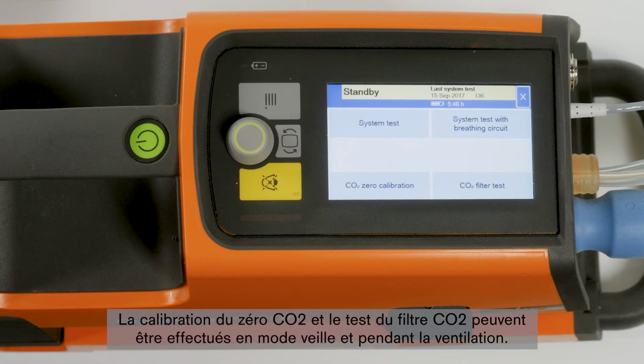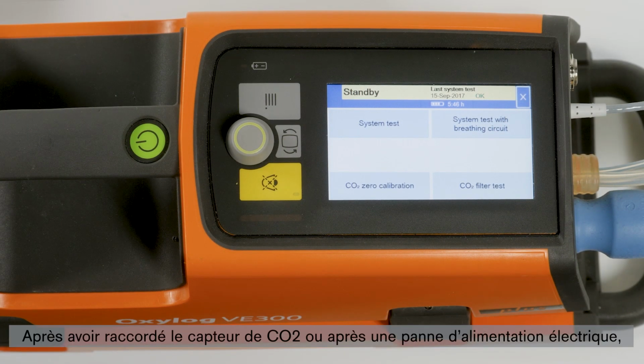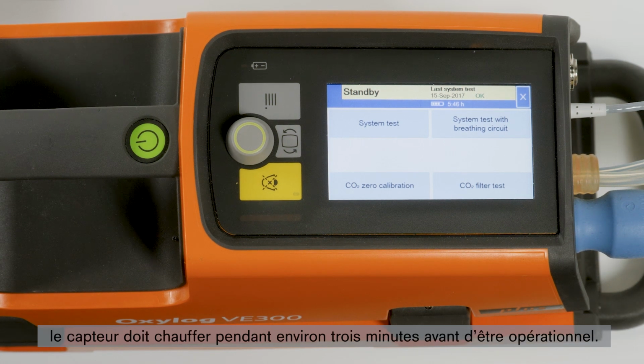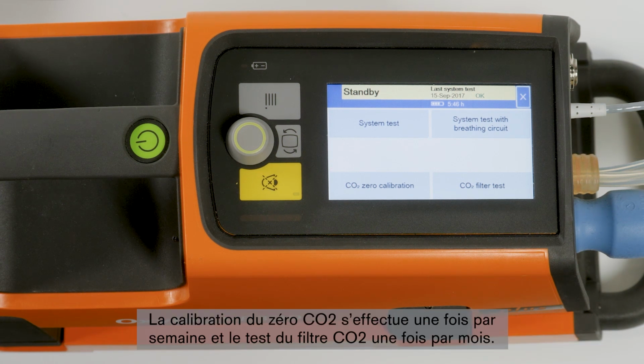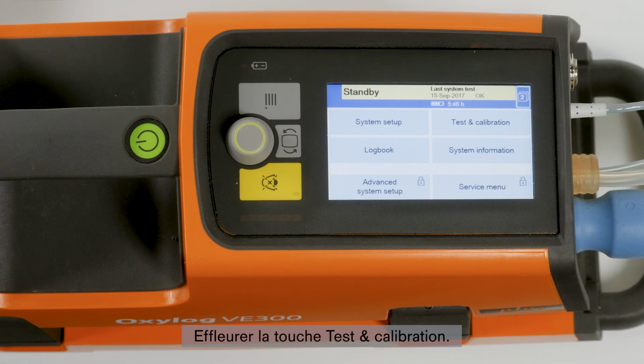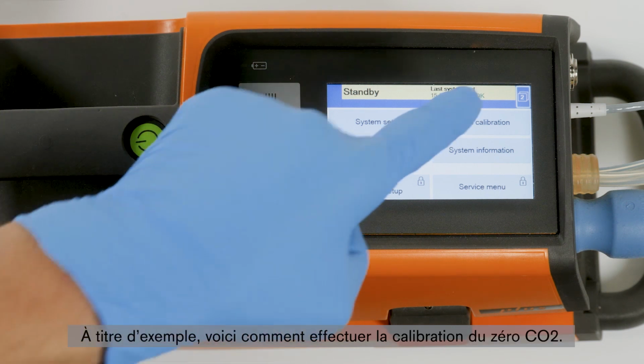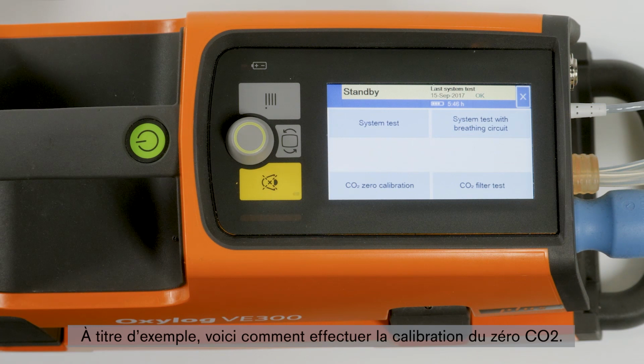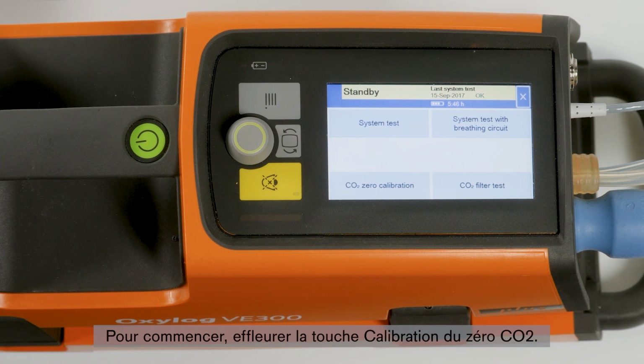The CO2 zero calibration and the CO2 filter test can be performed in standby mode and during ventilation. After connecting the CO2 sensor or after a power supply failure, the sensor must warm up for approximately 3 minutes before it is ready for operation. The CO2 zero calibration is carried out weekly, the CO2 filter test is carried out monthly. Touch the button Test and Calibration. As an example, we will show you how to perform the CO2 zero calibration.